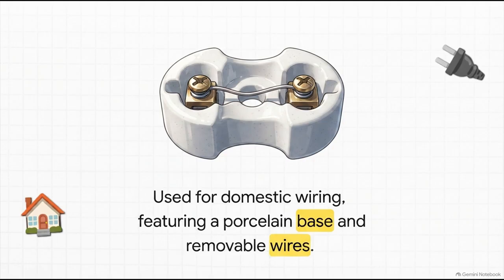First up, we've got the rewirable fuse. If you've ever poked around the wiring in an older home, you've almost definitely seen one of these. They're mostly used in smaller current circuits. The really neat part of this design is that it uses a porcelain base and a separate fuse carrier. You can easily, safely, pull the carrier right out of the base without even needing to shut off the main switch. Inside, it just holds a simple wire, usually made of lead, tinned copper, aluminum, or a tin lead alloy.